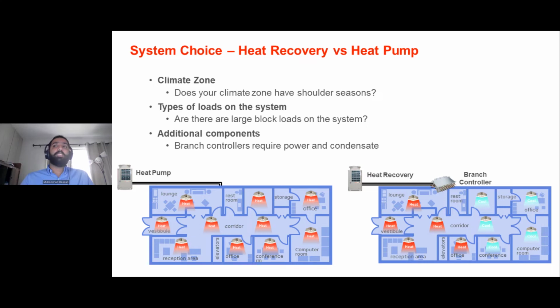Additionally, what are the types of loads on your system? Does your system have large block loads? We typically get asked a lot about putting IT rooms or other spaces with large block loads onto heat recovery systems. It's important to remember that heat recovery on a VRF system is typically suitable only for comfort applications. The condensing unit still has a cooling main or a heating main mode. So we size the system for full load. At part load, the system can be in cooling or heating main. And so the only source of refrigerant for the IT room or the gym becomes the recovered refrigerant from the other zones. And so as a result, in part load, the non-dominant mode can suffer. It's also important to remember that heat recovery systems, as previously mentioned, do have additional components. The branch box typically does require condensate removal and power, so it can be an additional cost on the project.